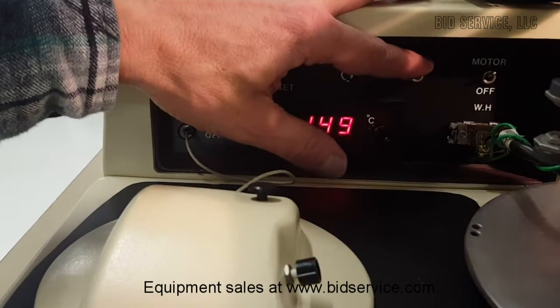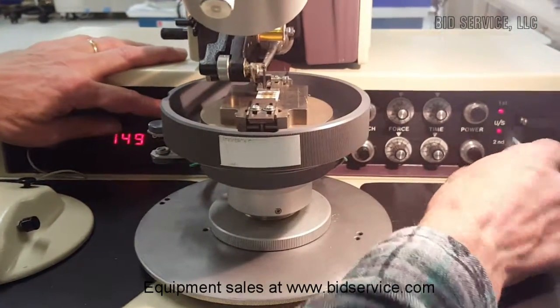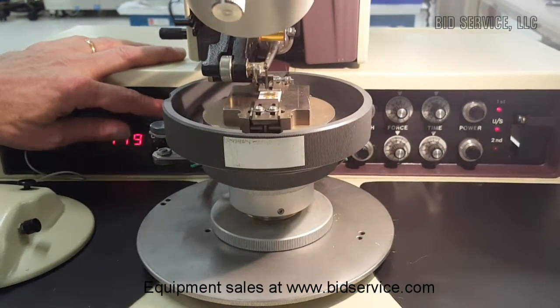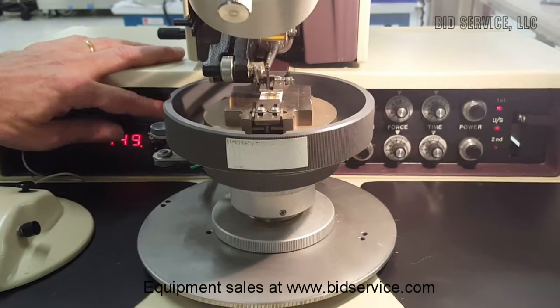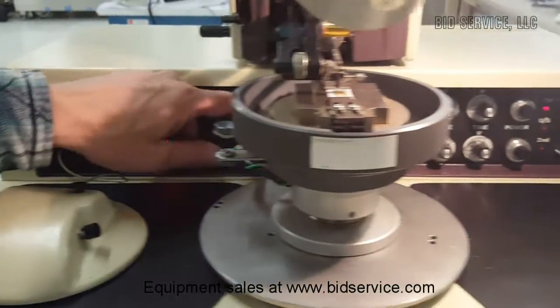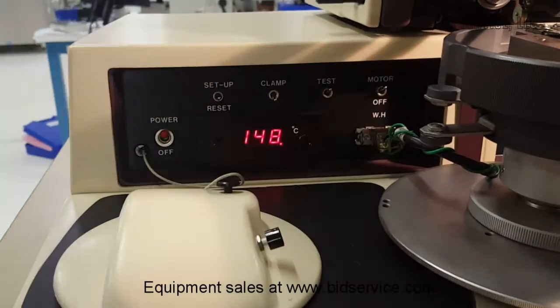We do have a test button here, and as we press the test, if you look over at the US light, that's when the ultrasonic transducer wedge setup is tuned. And then finally we have a motor on/off switch. If you need to do any maintenance, you can shut the motor off.